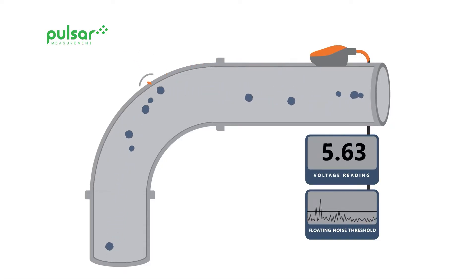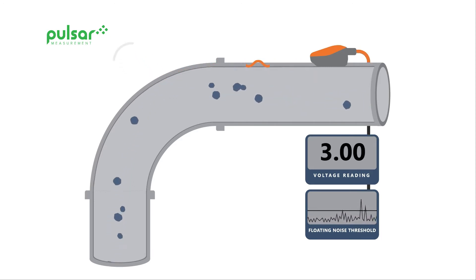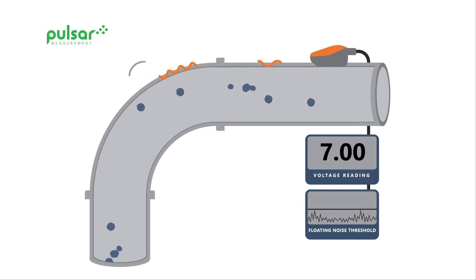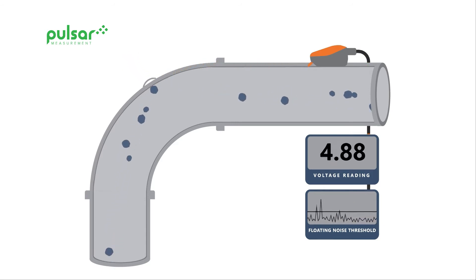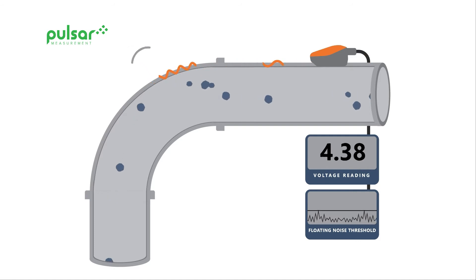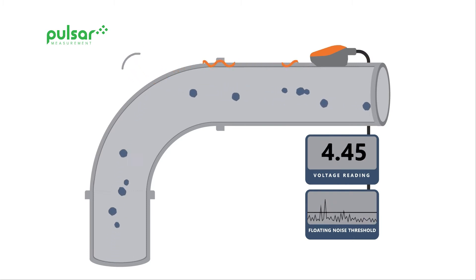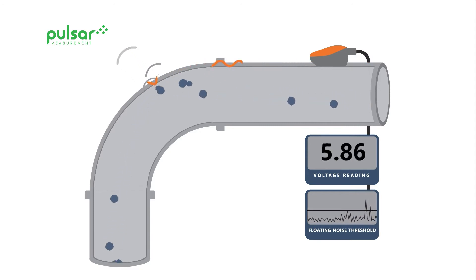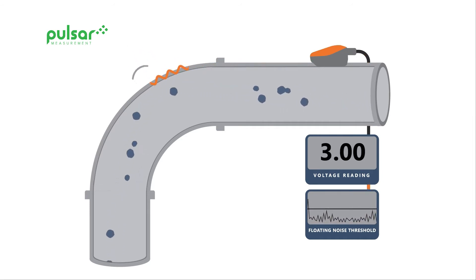Let's look at the technology behind the Sandalert. We use effectively two filters to make us independent of a flow regime and to listen only to the sound impacts. The first filter is the sensor itself, which works at a frequency that listens to impacts but will also pick up flow, as you can see from the animation. The second filter is an automatic threshold that sits below the low hiss of the flow but listens to the short-duration, high-amplitude impingements of the solids.